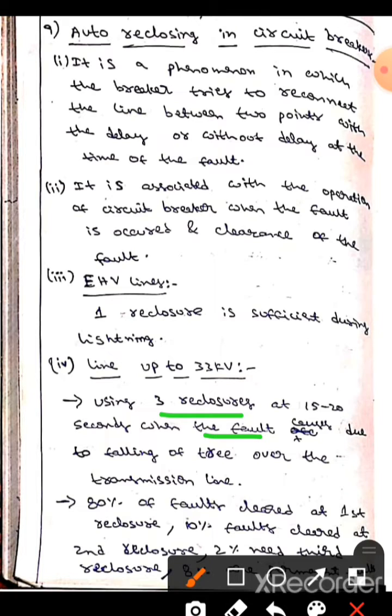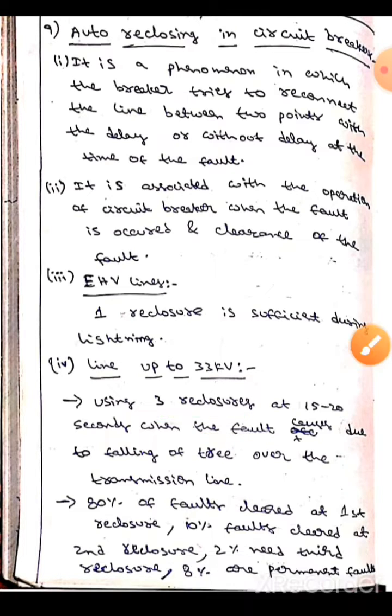80% of faults are cleared at the first recloser, 10% of faults are cleared at the second recloser, 2% need the third recloser, and 8% are permanent faults.